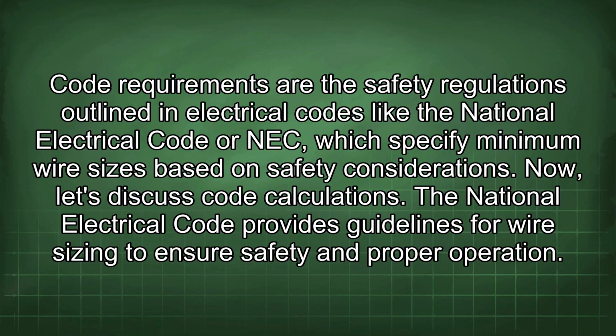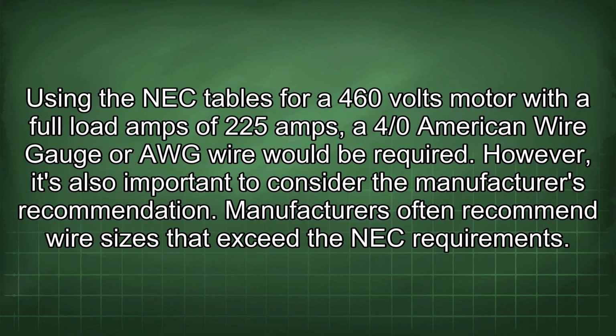Now let's discuss code calculations. The National Electrical Code provides guidelines for wire sizing to ensure safety and proper operation. Using the NEC tables for a 460 volt motor with a full load amps of 225 amps, a 4/0 American Wire Gauge, or AWG, wire would be required.